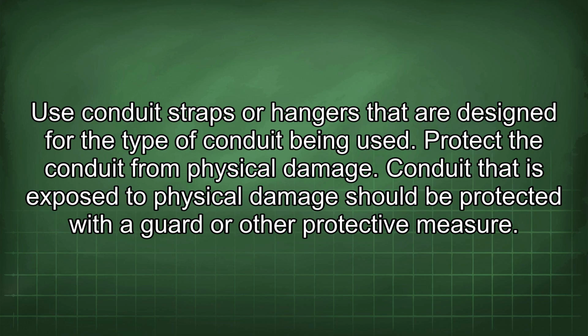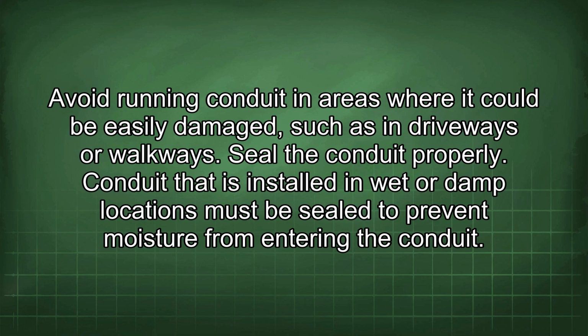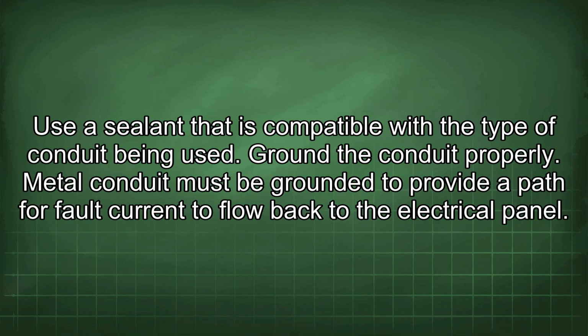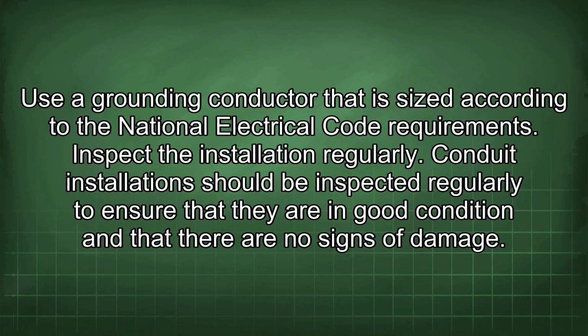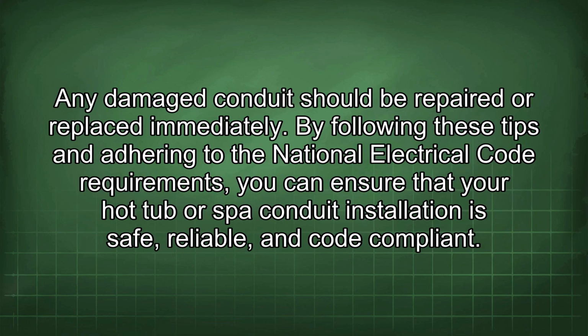Conduit that is exposed to physical damage should be protected with a guard or other protective measure. Avoid running conduit in areas where it could be easily damaged, such as in driveways or walkways. Seal the conduit properly. Conduit that is installed in wet or damp locations must be sealed to prevent moisture from entering the conduit. Use a sealant that is compatible with the type of conduit being used. Ground the conduit properly. Metal conduit must be grounded to provide a path for fault current to flow back to the electrical panel. Use a grounding conductor that is sized according to the National Electrical Code requirements. Inspect the installation regularly. Conduit installations should be inspected regularly to ensure that they are in good condition and that there are no signs of damage. Any damaged conduit should be repaired or replaced immediately.